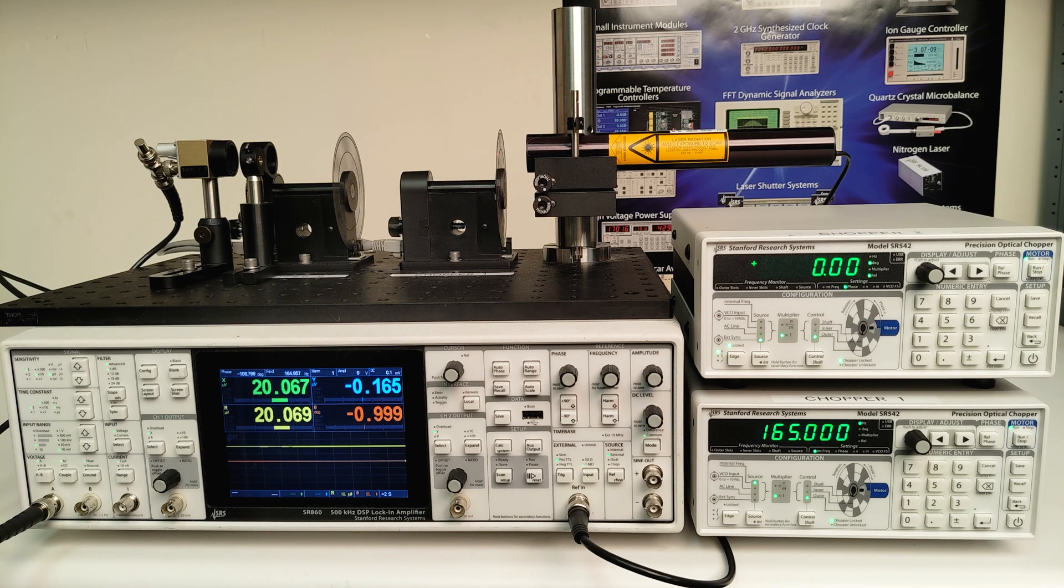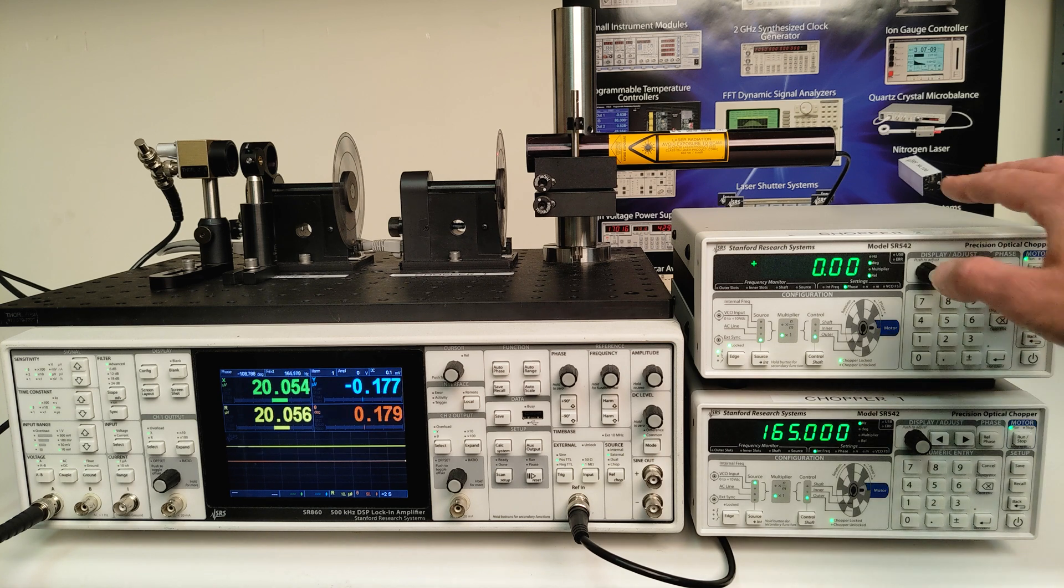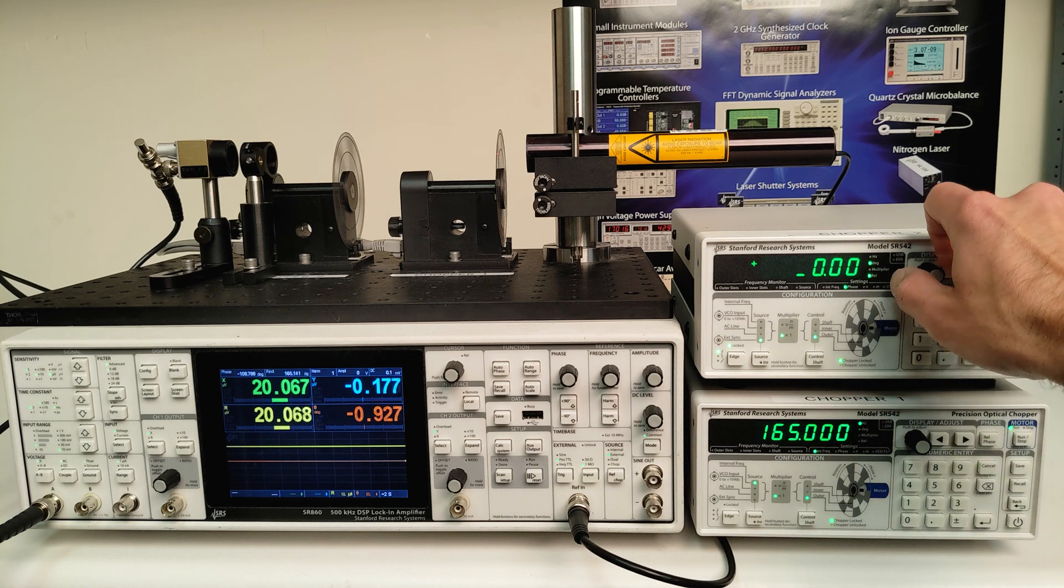And that's all there is to it. We've recovered a 50% duty cycle waveform for the dual chopped beam, and chopper 2's phase can now be used to tune the duty factor.